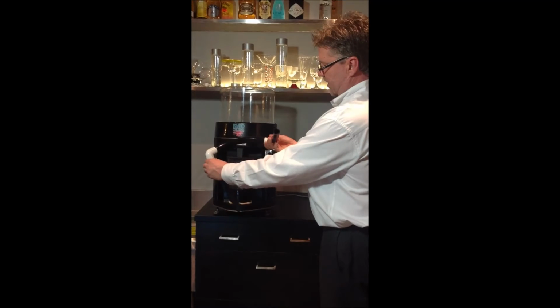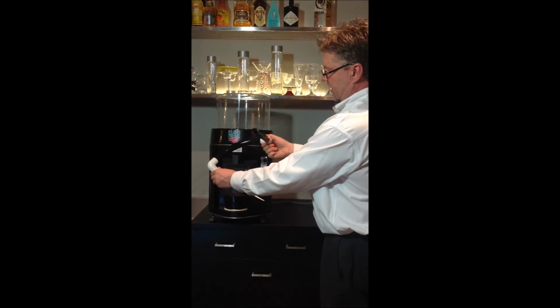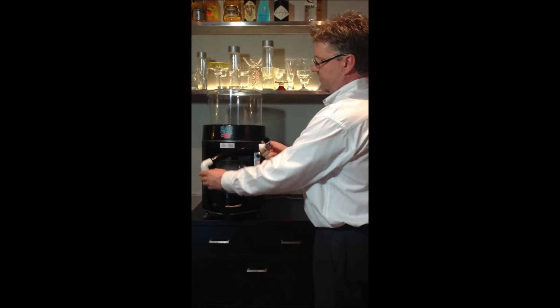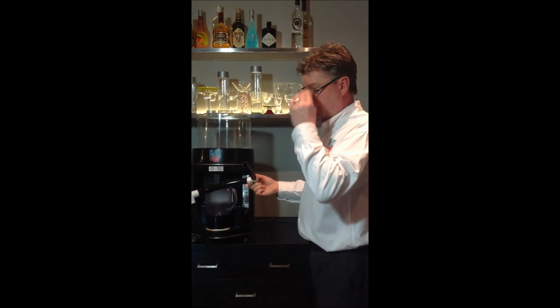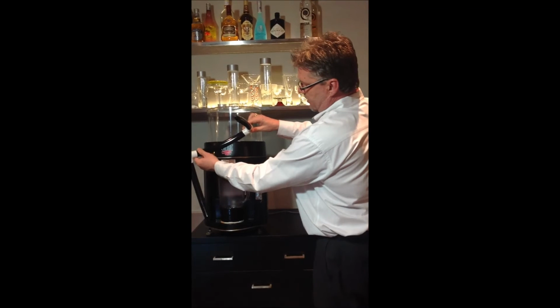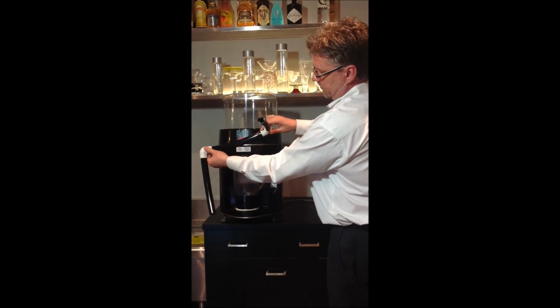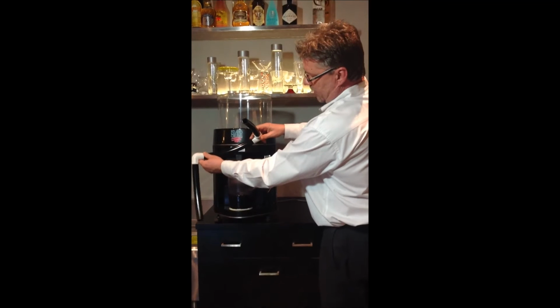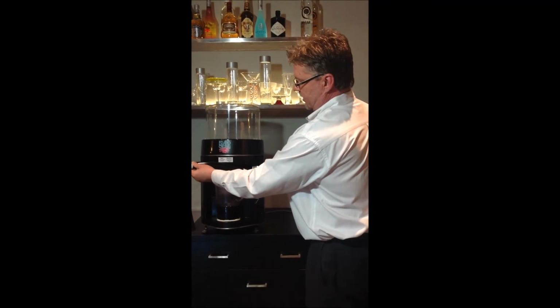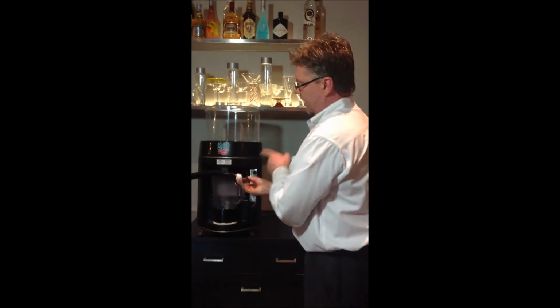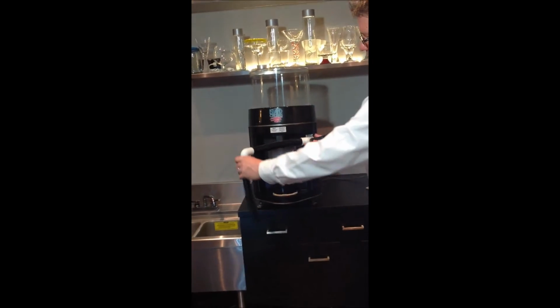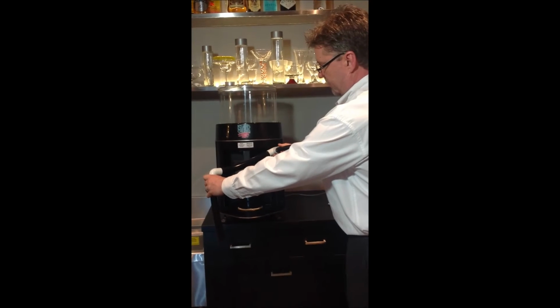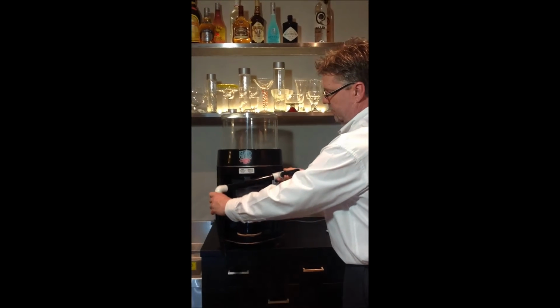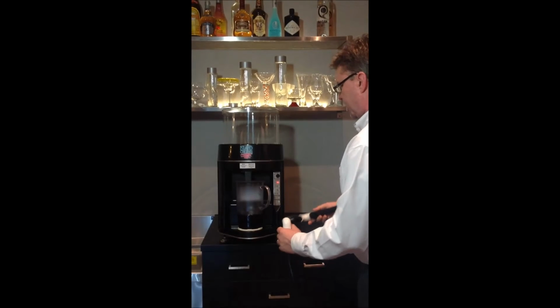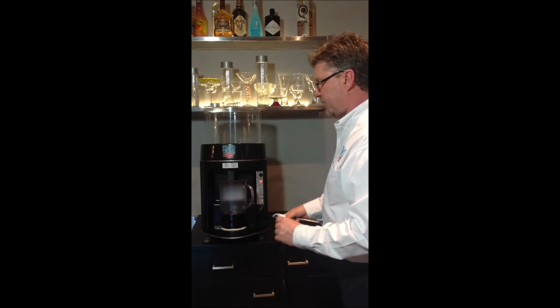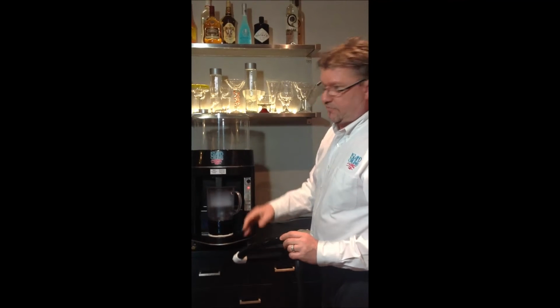Make sure you never have any spots in the hose where water can gather. Everybody knows water runs downhill, any plumber will tell you that. Make sure there's always adequate drainage and slope on the hose itself so no water can gather and trap anywhere along the line, because that's guaranteed to be where your problem is. Always make sure there's good drainage from the bottom of the machine to whichever drain you're running to, whether it's a sink or even sometimes a bucket on the floor. But the optimum system is running to a drain hole in the floor itself.